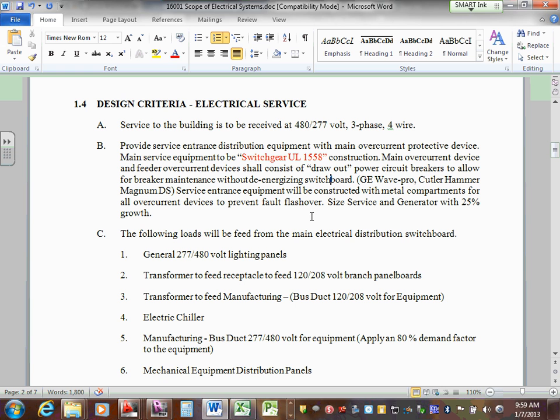We use 1558 gear sometimes in hospitals, and almost all the time on the main service gear for some of our bigger data centers, where you need minimal downtime for repair and maintenance. Jared will talk more about that 1558 gear, but it's more robust and takes more room. Power breakers are more sophisticated, and as part of your design, since it's a fairly expensive environment, sometimes we'll bring larger blocks of power out of that main switchboard and then redistribute with other less expensive methods, because it's expensive real estate.